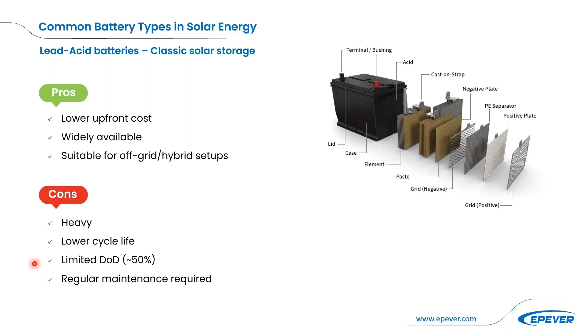But there are some trade-offs. They are heavy, they've got a shorter life cycle, and you can only use half of their capacity. We will look into the depths of discharge - basically, practically, you can use half of their capacity without cutting their lifespan down. And if you go for flooded types, maintenance is always there and you need to top up.